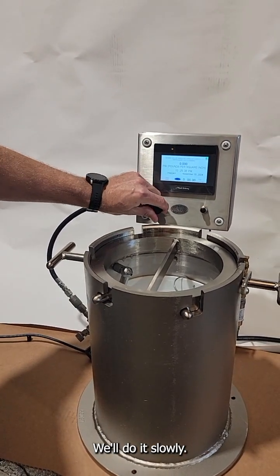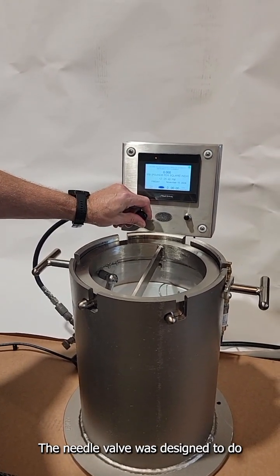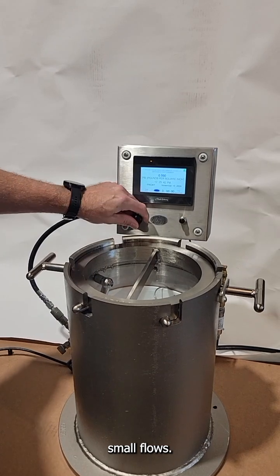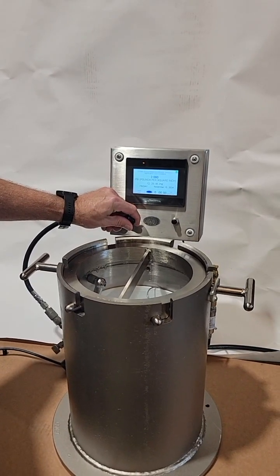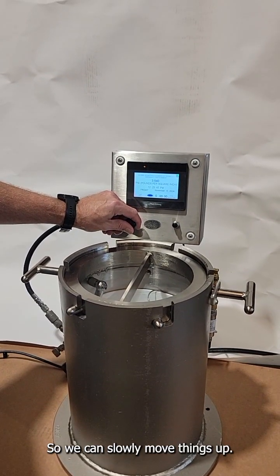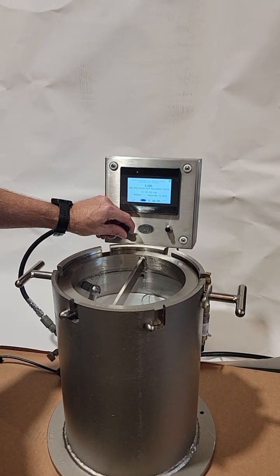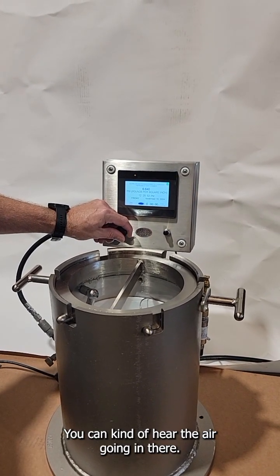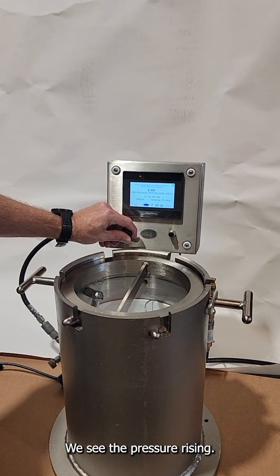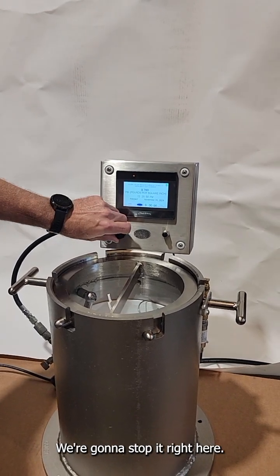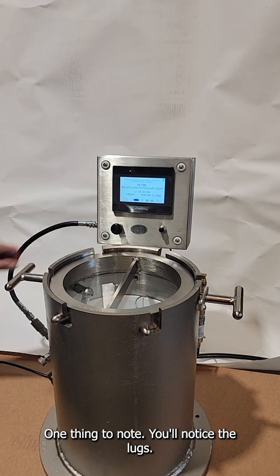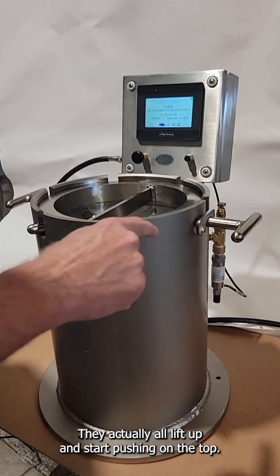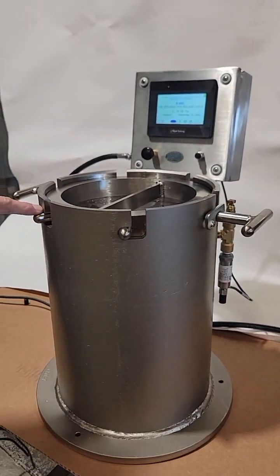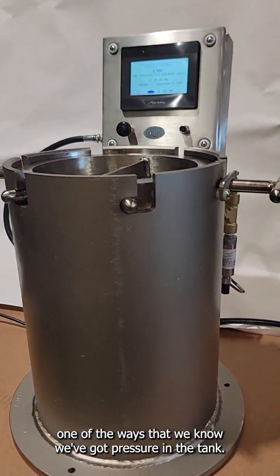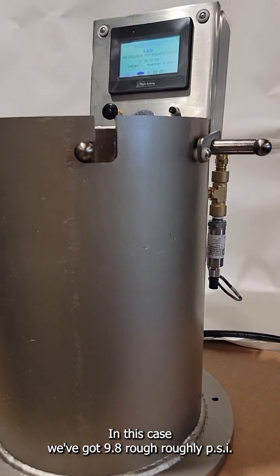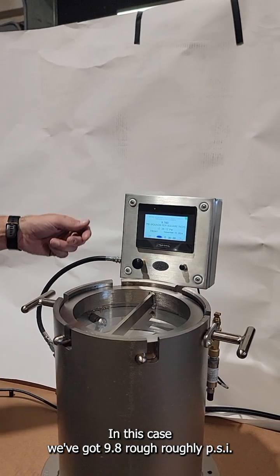We'll do it slowly. The needle valve is designed to do small flows, so we can slowly move things up. You can kind of hear the air going in there. We see the pressure rising. One thing to note, and I'm going to stop it right here: you'll notice the lugs all lift up and start pushing on the top. That's one of the ways we know that we've got pressure in the tank. In this case, we've got roughly 9.8 PSI.